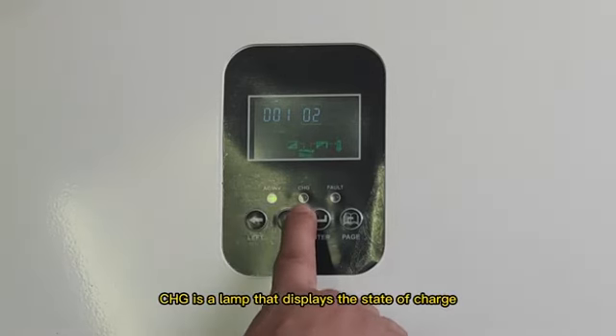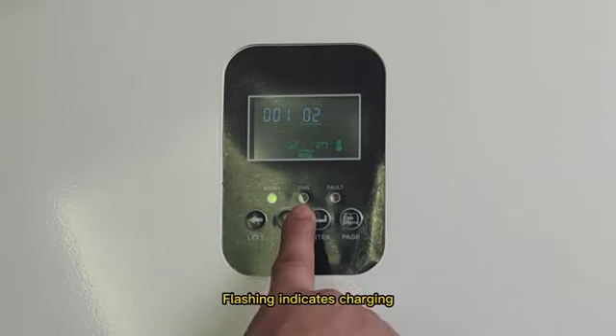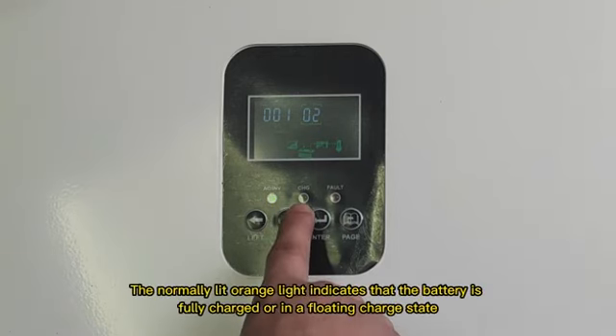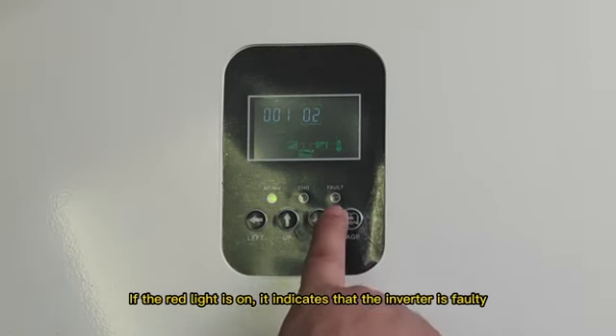CHG is a lamp that displays the state of charge. Flashing indicates charging. The normally lit orange light indicates that the battery is fully charged or in a floating charge state. If the red light is on, it indicates that the inverter is faulty.